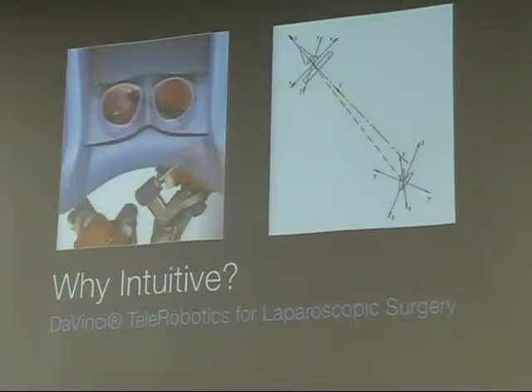What if you could take out that control and provide an image, which is what the physician would see in the eyepiece, and also provide input and control and be able to separate the two, and add whatever level of magnification I want, still have the same relative movement for what I see? Does everybody follow? So basically, you're transferring so you get the same frame of reference that you would with no magnification, with no apparatus, under very high magnification, and be able to work that way. So when I move the object, what I see in the camera is exactly what I'm feeling in the controls.